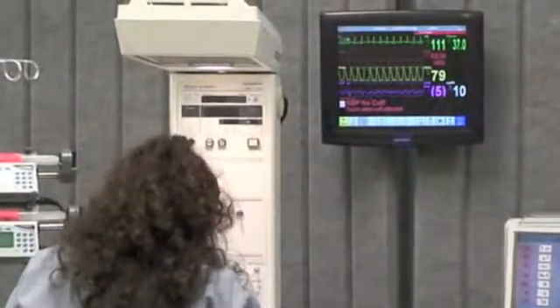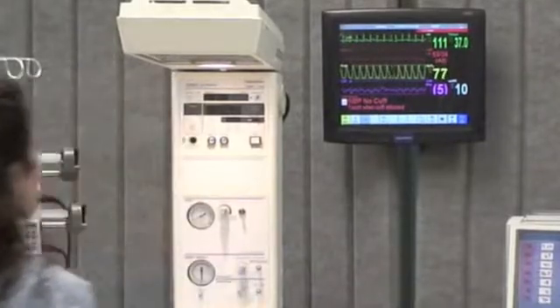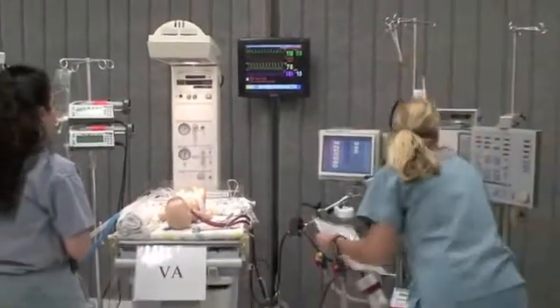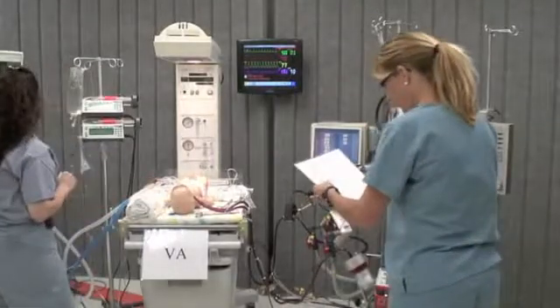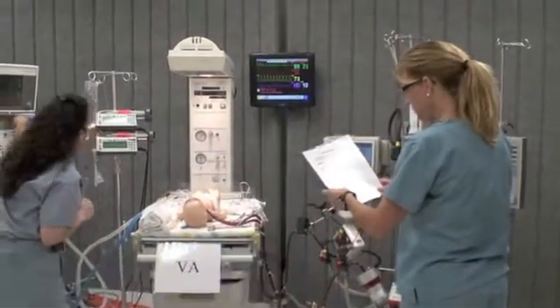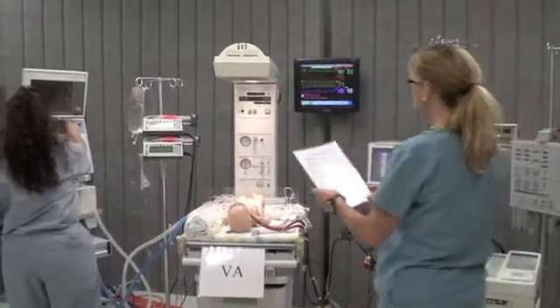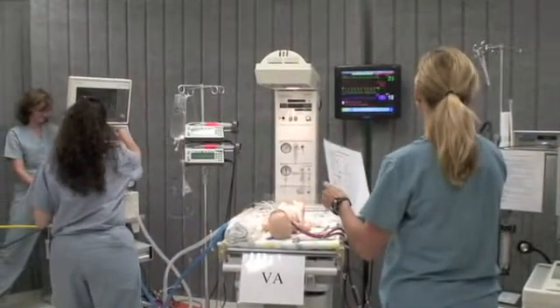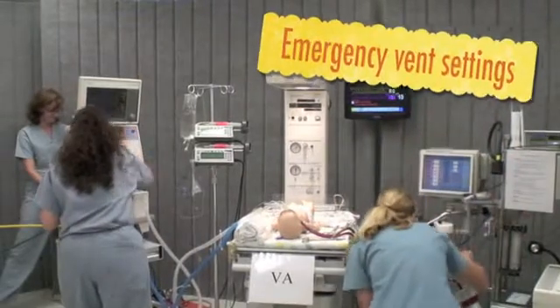Sats are at 80%. My patient's not getting better. I'm going to go up a little bit more, but I think maybe my post-membrane gas — my PO2 is only 41. Should I do anything with the membrane? I'm going to go up to 100%. I think there might be something wrong with my oxygenator.